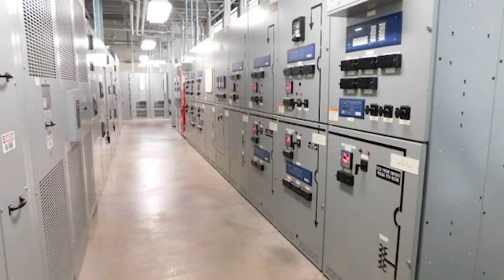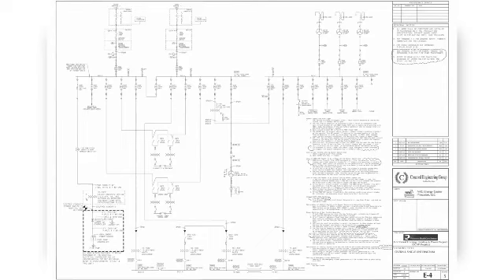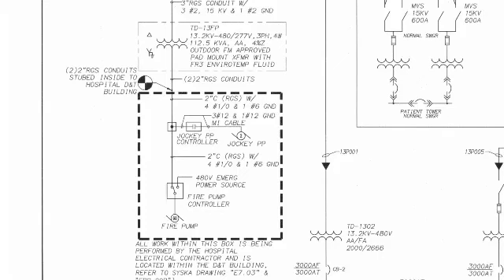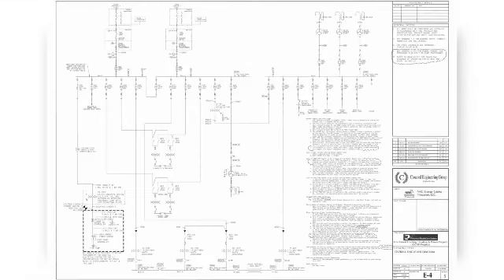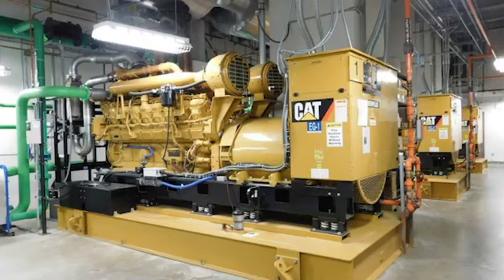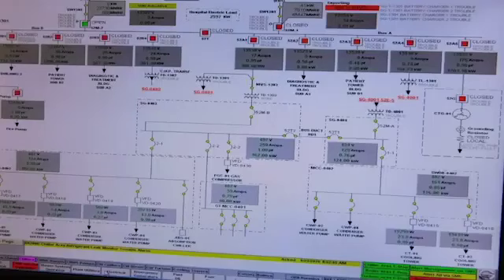The microgrid, and we'll show you the one line diagram here for a second. What we have is a main 13 kV bus. Feeding in on the A bus is a 4.6 megawatt gas turbine generator. And feeding in on the B bus is the 200 kilowatt solar array. And then we are also tied through a transformer to a 4160 volt diesel generator emergency substation. That bus itself is always energized, which gives us a lot of flexibility.